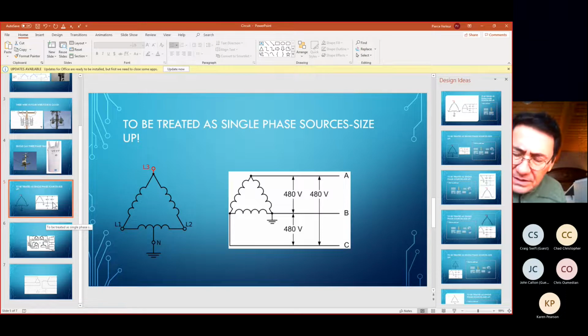this isn't corner, center, this is stinger leg is the term for it on the left. It's a delta secondary. I'm just showing the secondary of the transformers now. This is called stinger leg because one side is center tapped, the winding center tapped and brought to ground. This is a way of, again, saving a conductor. These are obsolete systems. They're not being installed on new equipment anymore, but they are still reasonably prevalent in the rural areas of California.